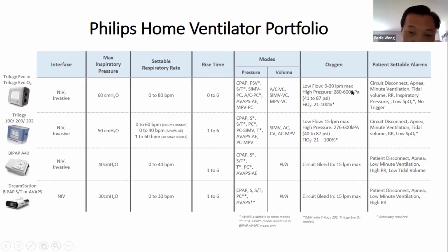And in case the doctor prescribes you supplementary oxygen, all of these devices can also add oxygen, but only this life support ventilator, when you add oxygen, will not cause any alarms because the oxygen is directly blended. There's a blender inside the machine to mix the air and oxygen together without causing alarms. But when you bleed in the oxygen using a connector, so this is called circuit bleed-in, it will cause nuisance alarms.